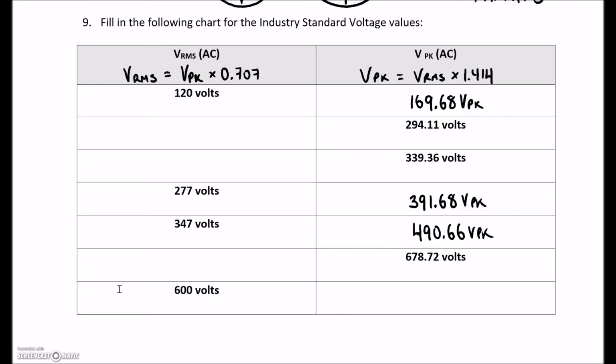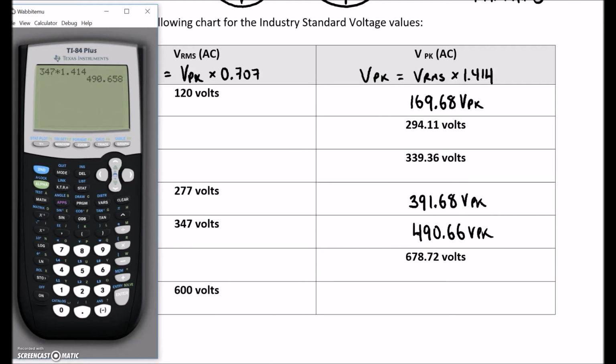Okay? Let's keep going. Say some donkey tells you to work on a live 600 volt bus. So what voltage is he actually asking you to work on? Remember that oftentimes our foremen are not the people who know what they're doing. They're just simply people who can push us to get the work done. You know what you're doing, and you know that 600 times 1.414 is an absolutely disgusting voltage of 848.4 volts.